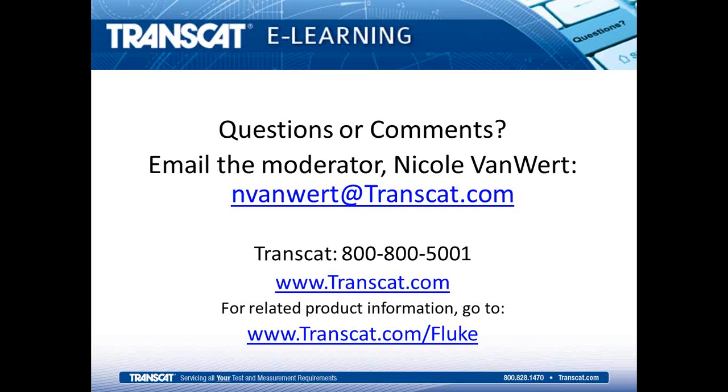If the uncertainty of what you're trying to do is a couple of degrees and you're within 100 degrees of ambient, you might be able to stay within that couple of degrees, but it would be advisable to try to do that in a fluid, in a microbath or something like that if you can.